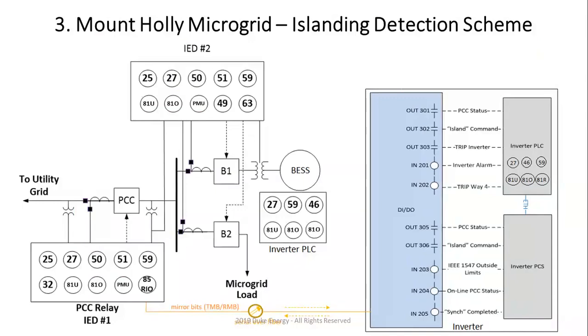Now, PCS is the power conditioning system. This is the part that actually switches the operating modes. And typically, every PLC and PCS have communication. Typically it's Ethernet, but it usually uses a proprietary protocol. So what we have done here is add this DIDO, which is nothing but a digital input, digital output block, with a certain number of inputs and outputs. And using mirror bits, which, like I said, have about a 2 millisecond delay between the PCC relay and DIDO, we can actually close some of these outputs and some of these digital inputs. Those are the inputs from the PCS and PLC.